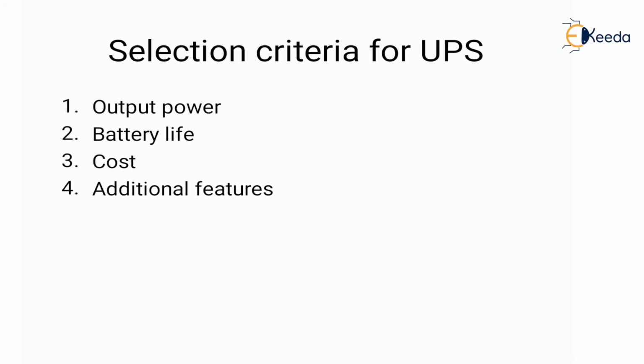Now let us see what are the selection criteria for UPS. First is output power. It is necessary to consider the size of load that is to be connected to the UPS. Once this is identified, the necessary rating of the equipment system can be determined. Next point is battery life. Now the manufacturer states the battery life for the UPS. However, the actual battery life is determined by how often the battery is used when there is an outage, surge, sag or swell. And each time the battery takes over, its useful life gets diminished.